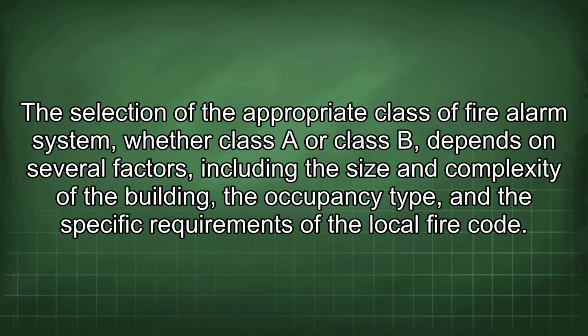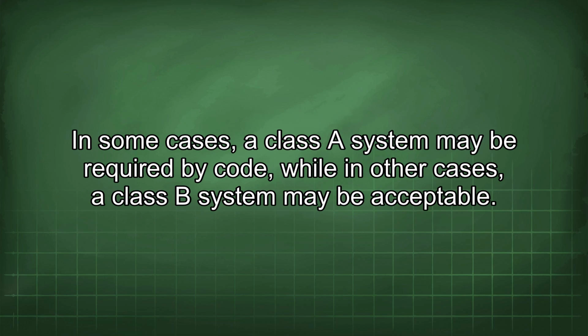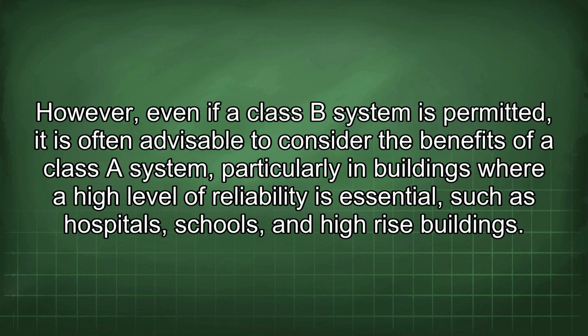The selection of the appropriate class of fire alarm system, whether Class A or Class B, depends on several factors, including the size and complexity of the building, the occupancy type, and the specific requirements of the local fire code. In some cases, a Class A system may be required by code, while in other cases, a Class B system may be acceptable. However, even if a Class B system is permitted, it is often advisable to consider the benefits of a Class A system, particularly in buildings where a high level of reliability is essential, such as hospitals, schools, and high-rise buildings.